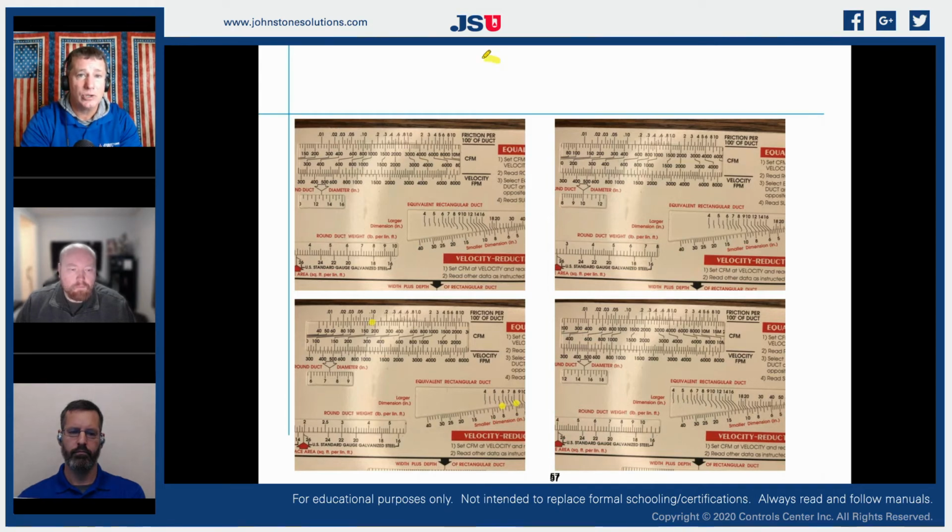So for the actual square rectangular duct, I'm going to run an 8x8 down to my last drop. I could also branch that down and run round if I wanted to, but typically when we're working with our plenum and with our actual transitional ductwork, we're going to keep it rectangular and then come off from it with boots to feed our individual units. So for this particular one, I would end up with an 8x8.